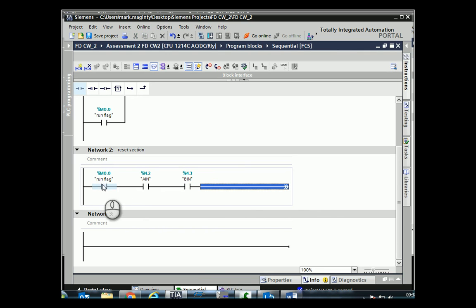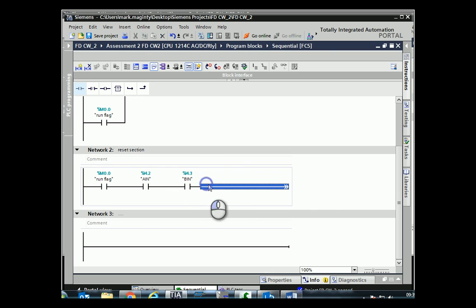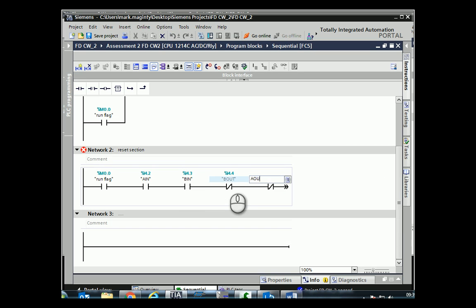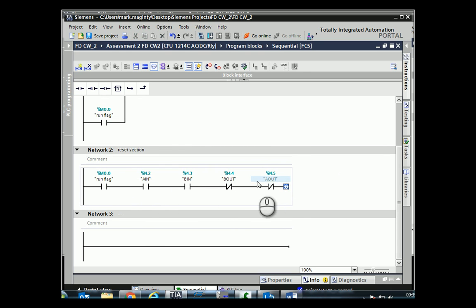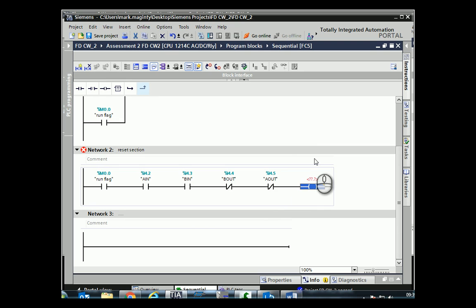So what we need to make sure is the run flag is on — the start button has been activated. As long as the two cylinders are in their retracted position — and you could go a step further and check that B-out and A-out aren't activated, just to be doubly sure. All these conditions must be met before the machine starts, and that will activate an output: M0.1.